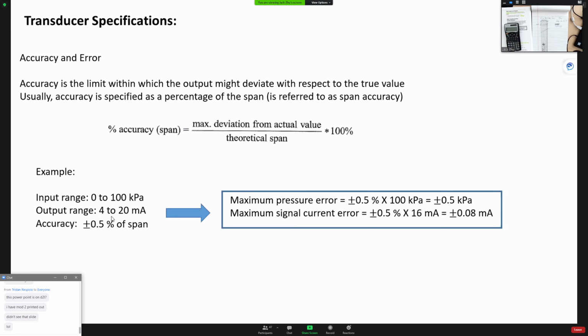For your output, for the current, it also has that accuracy. So the span will be 16 because it's 20 subtract 4. 16 milliamps times 0.5%. Your reading will be adding 0.08 milliamps or subtracting 0.08 milliamps. So that's where we can find the maximum reading and the minimum reading when you read a value down there. Here we give you how much you can go over, how much you can go low. So that's the accuracy of the transducer, the same as what you learned before as the meter.